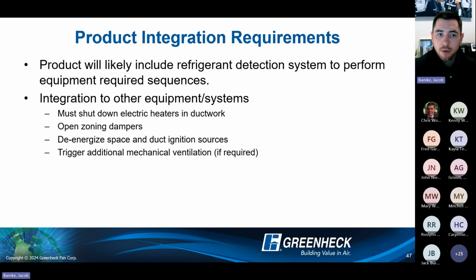So first example, you must shut down electric heaters in the ductwork if we experience a leak at the unit with ducted systems. All zoning dampers have to be opened up, again, if you want to count those spaces and avoid overpressurization of ductwork. That's important. You have to de-energize space and duct ignition sources, which we'll talk about next slide. And then if you need any additional mechanical ventilation, if the space is too small for that refrigerant charge, that must be triggered at this point as well.